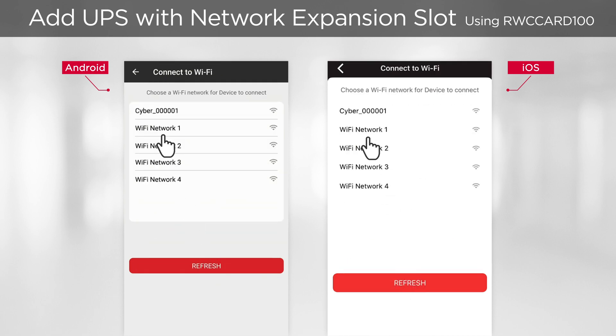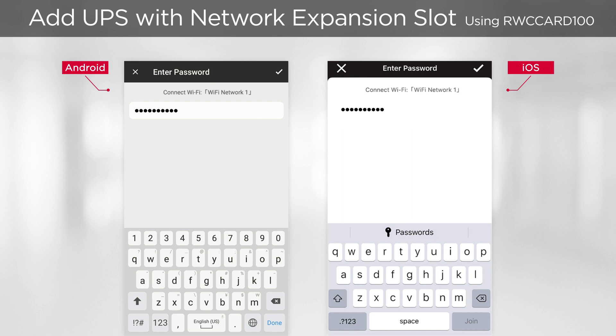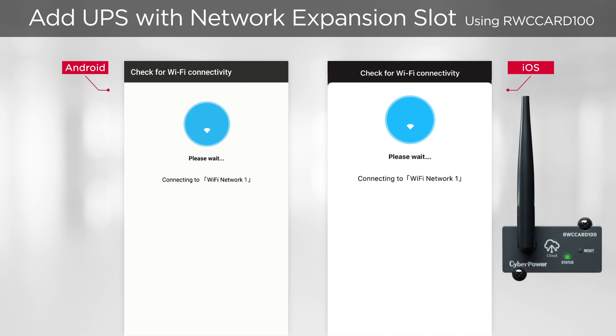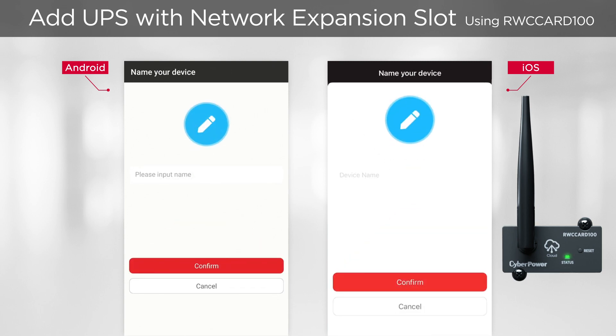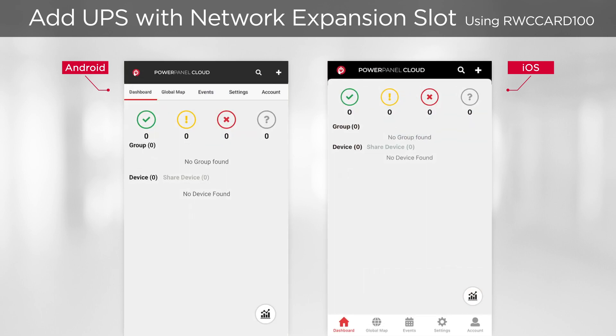You will see the Set Wi-Fi button, which allows you to connect the card to your Wi-Fi network. Tap the button, select your Wi-Fi network for the card to connect, enter the password of the network, and connect. The system will check the Wi-Fi connectivity, and the status LED of the card will be flashing green. Once connected, the status LED will become solid green and the UPS will be added to the cloud. Name the UPS and tap Confirm. You will return to the dashboard and the UPS will be displayed after a while.